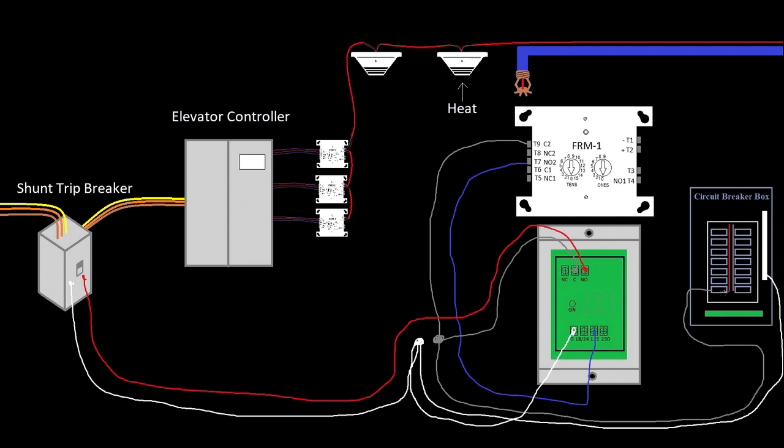So it's got a circuit breaker that somebody can walk up and just turn off. There's nothing supervising this power currently, so if somebody turned that off, shunt trip isn't something that activates very frequently, so that could stay off for a pretty long time before anybody noticed it.